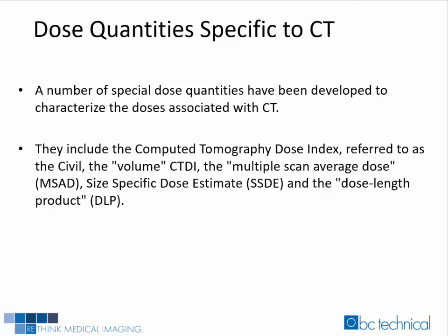A number of special dose quantities have been developed to characterize the doses associated with CT. They include the computed tomography dose index, referred to as the CTDI, the volume CTDI, the multiple scan average dose (MSAD), the size-specific dose estimate (SSDE), and the dose length product (DLP).